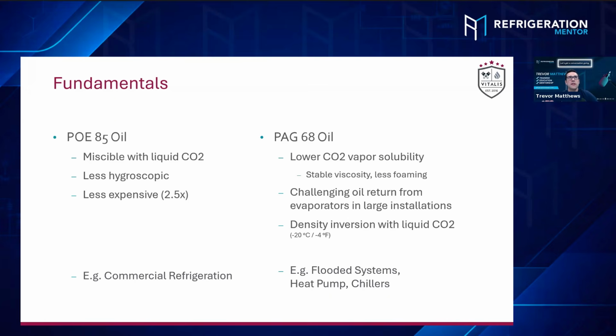Okay. So that means that with the PAG 68, it separates, like the oil's on the bottom at the right saturated temperature and the CO2 is on the top. But with POE 85, for an example, that can be just mixed together and that's coming back to your compressor, which is a no-no. Okay, great. Yeah, I mean, you want to have that steadily coming back, and that's working with POE pretty good. On the other hand, it's more difficult to operate flooded systems with POE oil, because you need to be sure to separate the oil out of the liquid. Makes sense. For that, you typically have these little tiny internal heat exchangers to evaporate all the time a little bleeding oil mass flow.